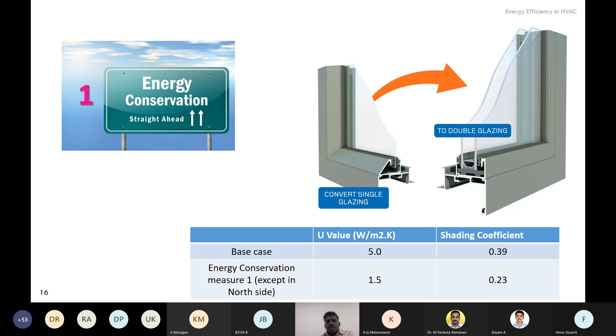As we discussed, by reducing the U value, we are reducing the heat ingress by means of conduction. And the solar coefficient, earlier in the base case, was 0.39, and we are now going to consider 0.23. Now, in the double glazing, through a special coating, we can reduce the shading coefficient. You can see in many buildings, people apply some kind of shade, some stickers or some film to reduce the shading coefficient only, and it will not reduce the heat energy conducted through conduction. Okay.